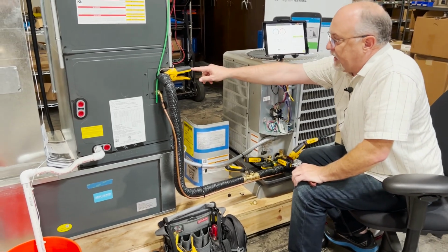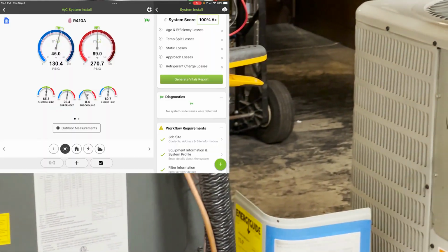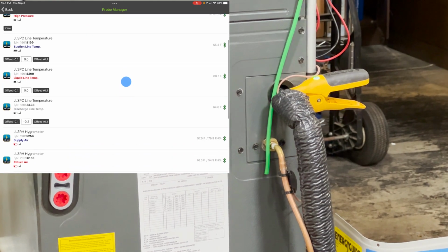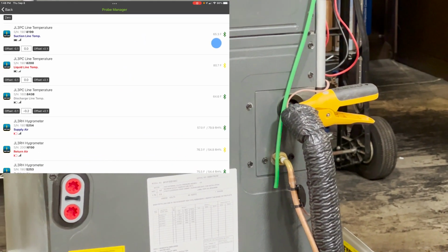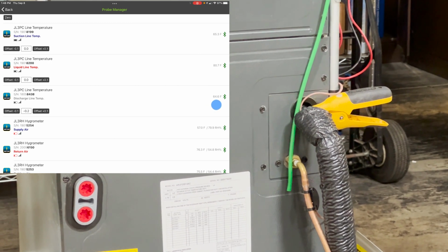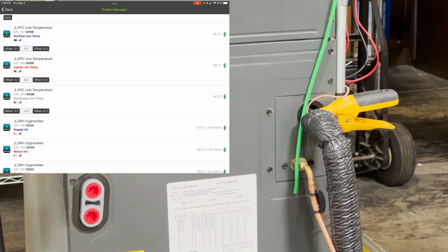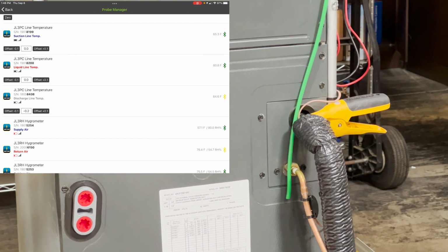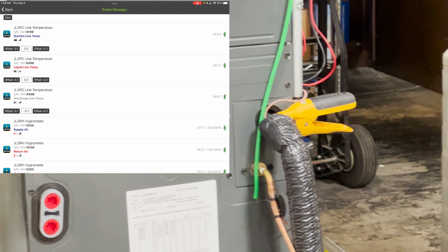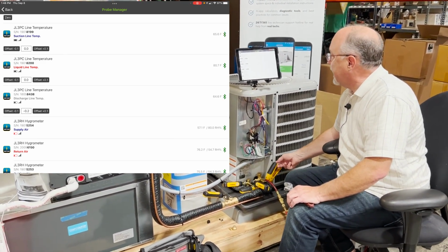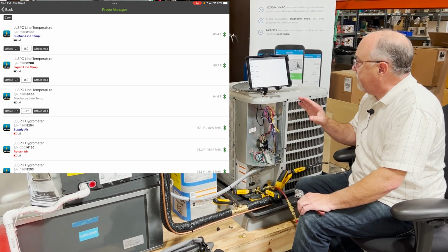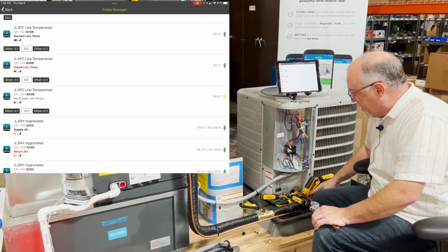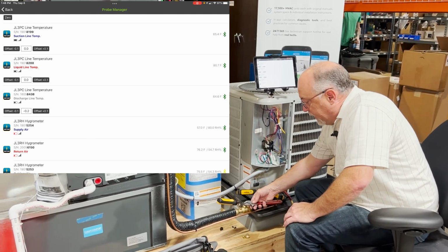Now, I also installed a second clamp here for just a minute, and I want to show you something on that clamp real quick. This is my discharge line temperature clamp. If we scroll up here a little bit, you can see my suction line is about 65 degrees, and down here I'm about 65 degrees also. It's actually 64.6, but that's just a little difference in the two readings. So there's no temperature difference really between this clamp and this clamp on my suction line. They're pretty much identical, and that's the way it should be. In fact, it should actually get warmer from this point to this point because there's additional superheat gained in the suction line. So I'm going to start throttling this down here for just a minute.